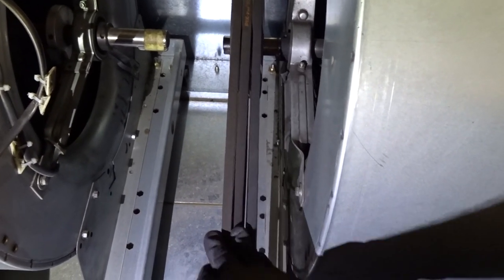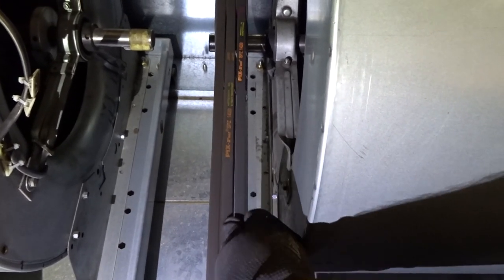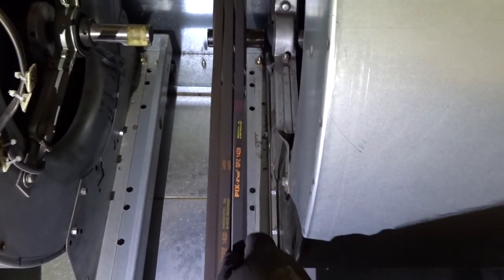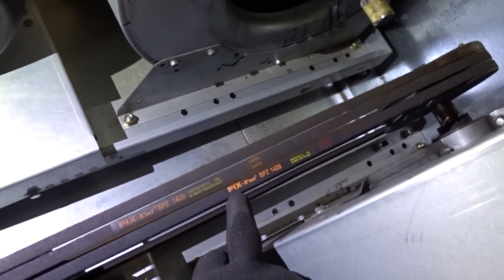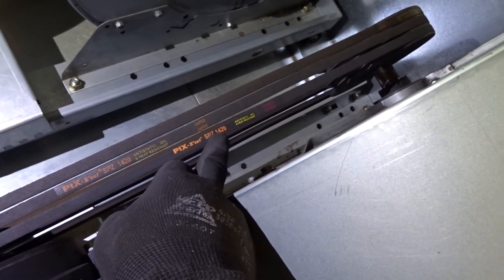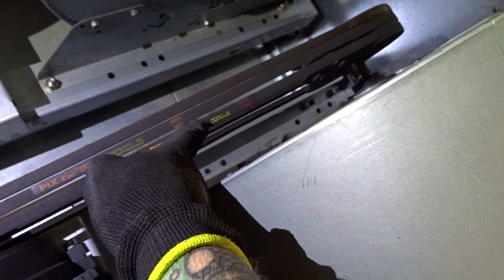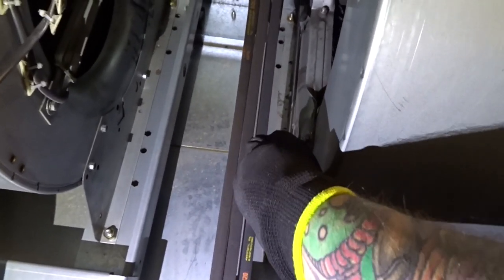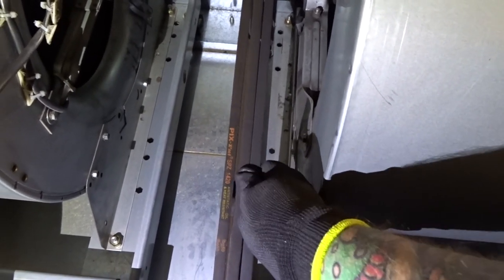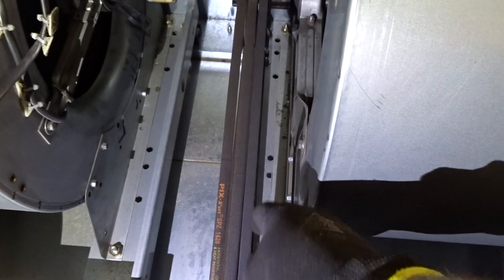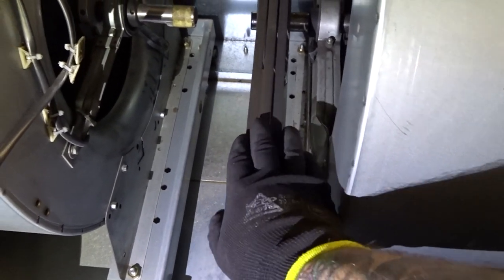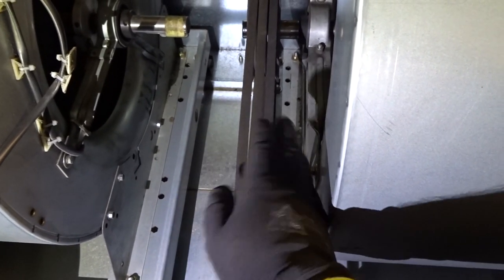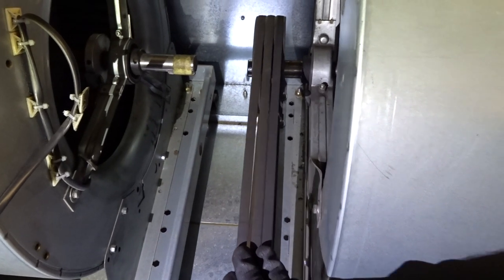They all seem okay to me. I'll just slowly pull them through, pull them back on itself. As you can see there, these are SPZ 1420s anti-static oil and heat resistant belts. What I'm looking for here is any signs of splitting. I'm looking for any fraying from the sides. If the belts are not lined up correctly then one side will possibly wear more than the other side.